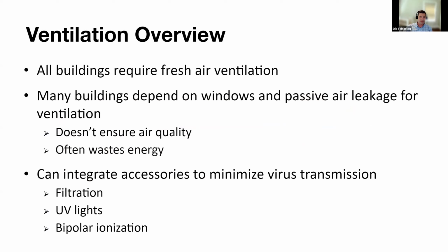So going to ventilation, just a ventilation overview. All buildings are going to require fresh air. Many buildings depend on windows and passive air leakage for ventilation, but this doesn't ensure air quality because now the air coming into your space is not filtered, and this often wastes energy because on a 95-degree day, you have 72-degree air getting taken over by 95-degree air coming in through the windows. And if you're using a ventilation system, that's when you can integrate accessories to minimize virus transmission, such as filtration, MERV 10, MERV 13 filters, UV lights, or bipolar ionization.